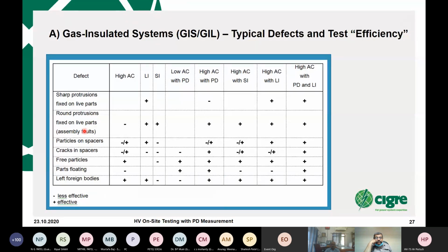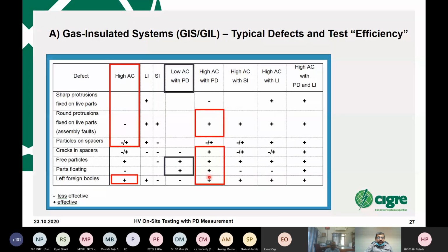Now, GIS and GIL testing again, there are typical defects, like sharp protrusion, particle on spacers, and so on. High AC voltage means this is not normal operating voltage, this is higher voltage on site. And as you can recognize, due to the physical behavior, the plus means it's well detectable by breakdown or PD, in this case by breakdown. And then the other thing, as we are talking today, is partial discharge. Low AC means like a monitoring system, low means under operating stress. So this can be identified quite easily. And for commissioning, with a high AC voltage test with PD, you can even detect particles on the live parts. But you see there's still some which are not possible, again, due to physical reasons.